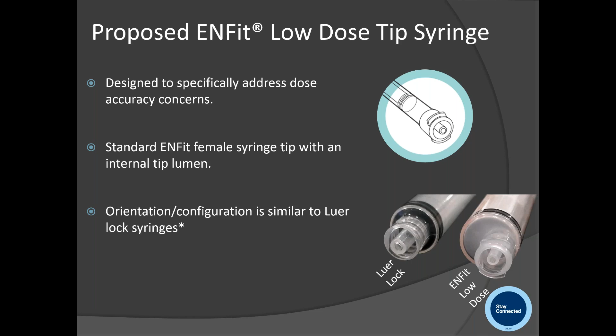So what we did is we did performance testing on these low-dose tips, and we were able to demonstrate that the ENFit low-dose tip was consistent with enteral and oral tip syringes. We actually looked at 3 different versions from various manufacturers because there is no design standard for an oral tip syringe, and we wanted to get a baseline for what that looked like. And in fact, we found that it was within plus or minus 10%, negative 7% to a positive almost 10%, in terms of dose accuracy. By the way, we were looking at a 0.2 ml dose of medication delivered in a 1 ml syringe, and we were looking for that to be plus or minus 10%.